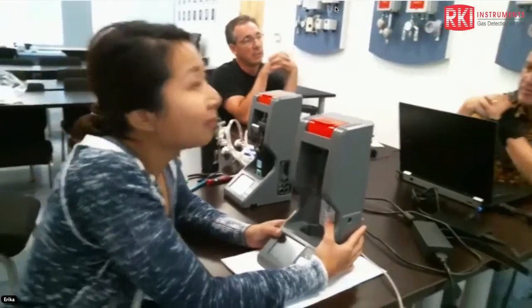Most single instruments won't need more than 3 gas cylinders, but if you have 5 or 6 docks connected together and multiple instruments with multiple sensors, you can connect everything at once, and the dock will select the right gas and apply it when the calibration or bump test is being done. So for a rental company with a permanent docking station, switching sensors in and out, it means they don't have to switch gas bottles around every time.